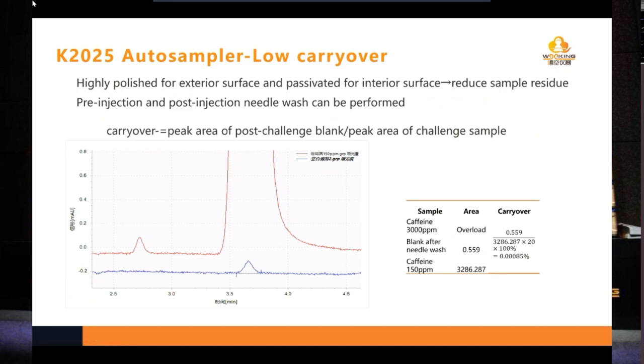To have a lower carryover, the needle is highly polished for the exterior surface and passivated for the interior surface. And the carryover will be even lower when the needle is washed before and after the injection. And we also did a test. In this test, we used a high concentration of caffeine.